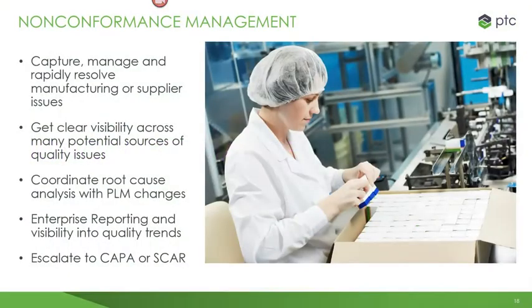Nonconformance. The Windchill Nonconformance Management best practice is a closed-loop nonconformance process, a compulsory quality process which enables companies to capture and process all types of internal, product, material, and process nonconformances. The NC procedures shall address the identification, documentation, evaluation, segregation, and disposition of nonconforming product. The evaluation of nonconformance shall include a determination for the need of an investigation and notification of the persons or organizations responsible for the nonconformance.